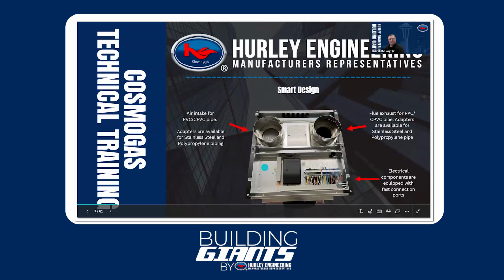And so you can see here from the top, this is our intake air, and you can see that filter. What I mean by having two uses without cleaning is the filter extends all the way to this lower portion here. So if I were to pull it out and spin it 180, I'd be using the other half of the filter. Now, if I flipped it over, then it would be going the wrong direction. So you can't do that and get the different uses, but spinning it around 180 degrees and using it twice is perfectly acceptable. So you'll see our exhaust connections are here on the top as well. And then all of our electrical connections are on top. So most of your connections will be made at the top, your venting and your electrical.